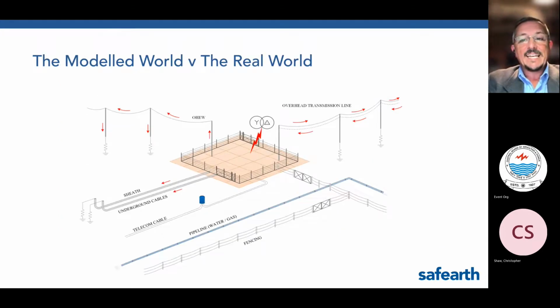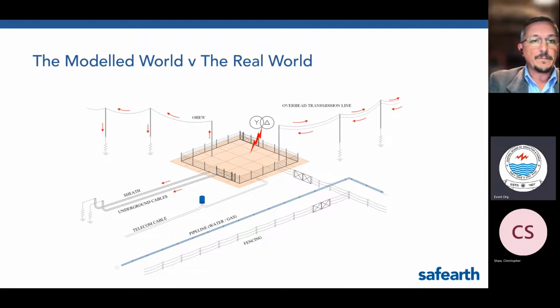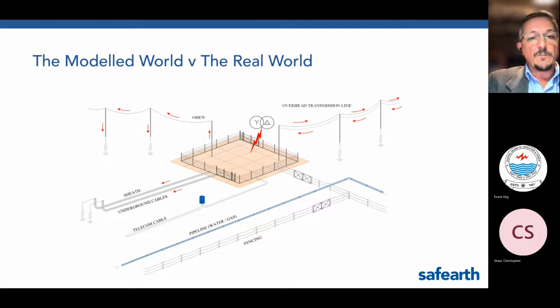So that soil resistivity data is then used for modelling. It's essential for us to do modelling. And you can even model and try and estimate all of the step and touch voltages and transfer voltages. But is that modelling approach accurate? Is modelling actually able to prove safe? Some people certainly believe it is, and some countries rely extensively on soil resistivity testing, simple electrode resistance measurements, and computer modelling. But perhaps that's a little bit indirect, and there are now options for more direct measurement of the earthing system that can create more confidence around whether it's doing its job or not.